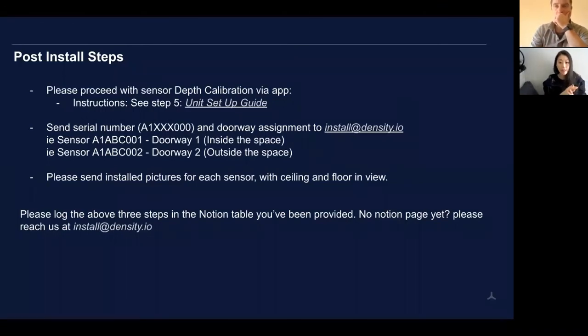Once everything is installed online, the white LED is on and the 4 red laser lights are working, please send me the install picture, much like the pre-site walk photos, so we can match those diagrams to make sure everything is installed correctly and have a record of what that sensor looks like within the space for the customer. All of this gets uploaded to the same form and table you had provided before in Notion, so once you have access to that, all the post-install information also goes into that sheet.